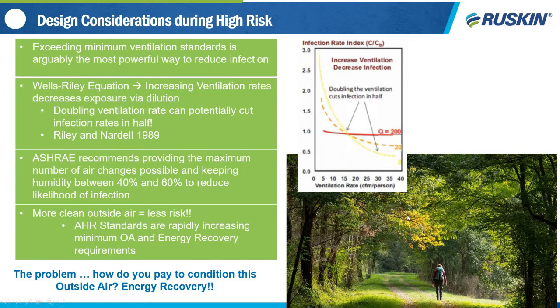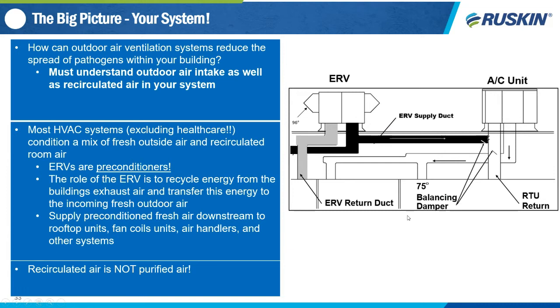Before we dive into the ERV itself, I want to take a step back and look at your system. We need to understand the ERV's role in the system before we can dive into the ERV. The picture on the right is a common ERV duct configuration. I'm going to walk you through this picture. What you see is the ERV taking in, in this example, a summer day, 96 degrees outside. The ERV takes in that 96 degree outdoor air.